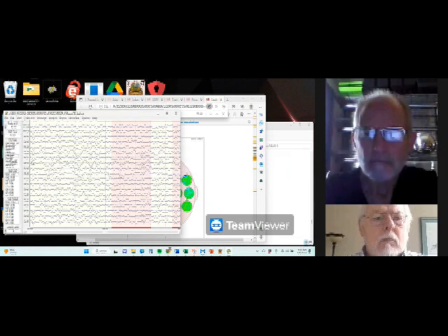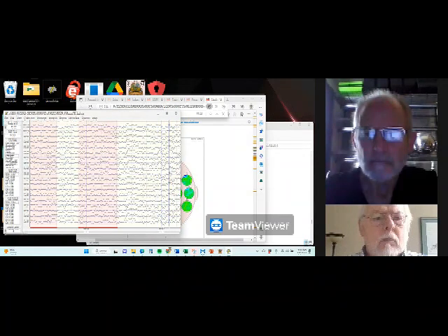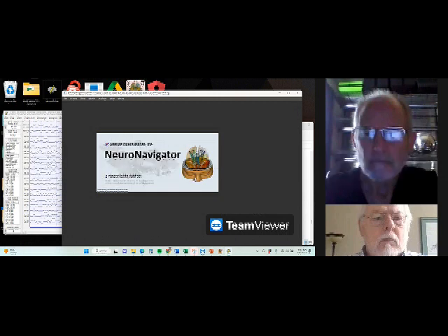I got a clear selection. I'm going to go to view, but I've already done it. So I just have to, after I selected it, drag my mouse over it. Then I launch the NeuroNavigator for the section I just selected. And then you go millisecond by millisecond through that selection to look at where that event is coming from. You can go through the whole record if you want.